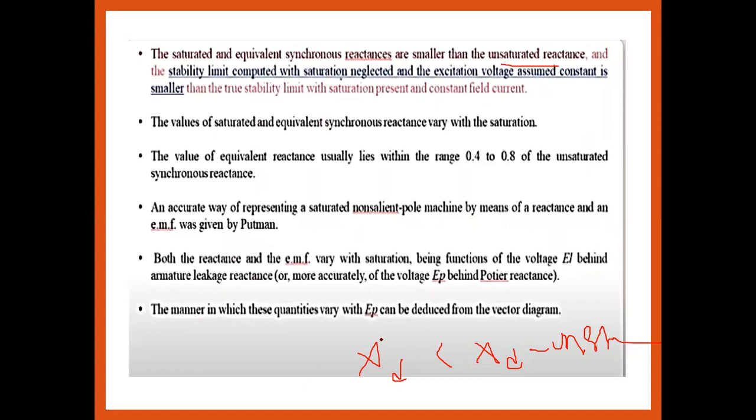The saturated and equivalent synchronous reactances are generally smaller than the unsaturated reactance, and the stability limit is generally computed with saturation neglected and the excitation voltage assumed constant, which is smaller than the true stability limit with saturation present and constant field current.